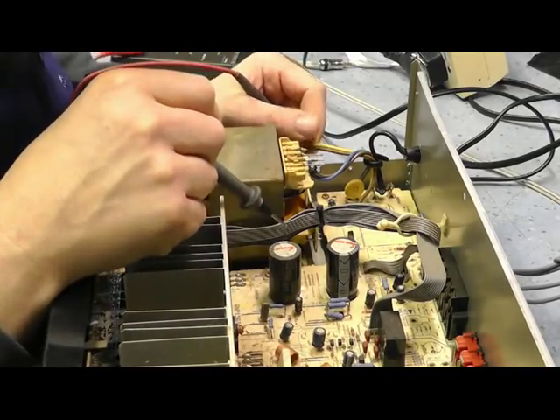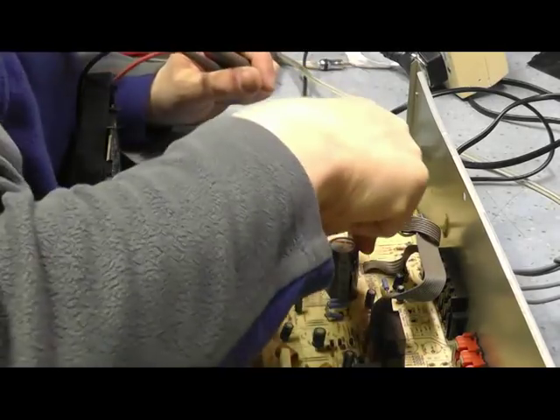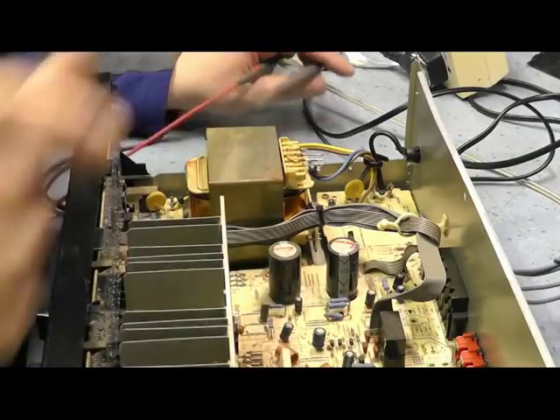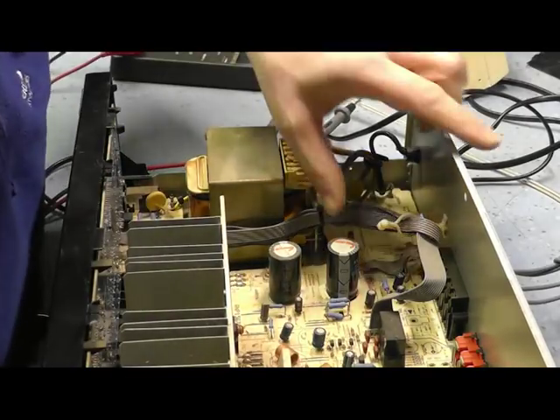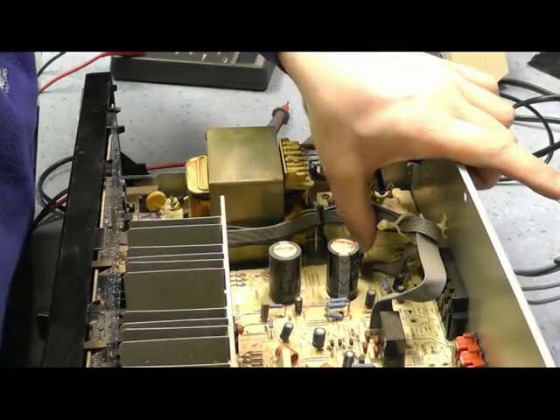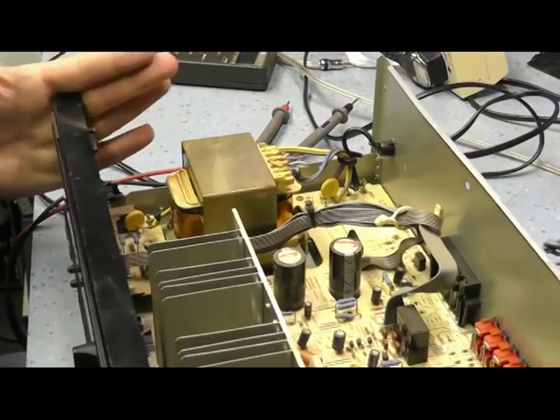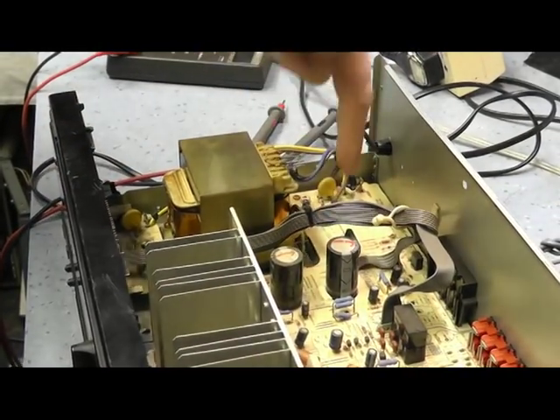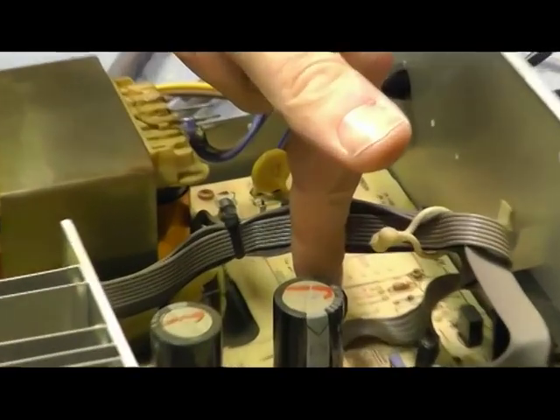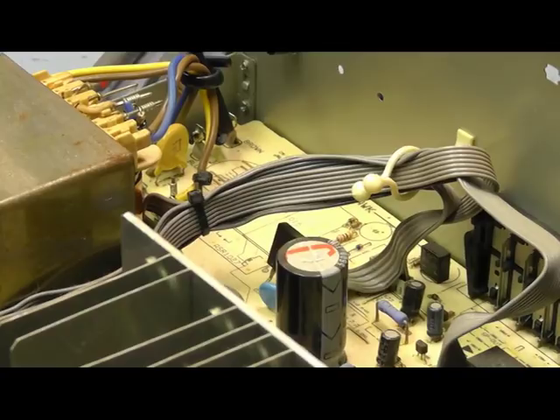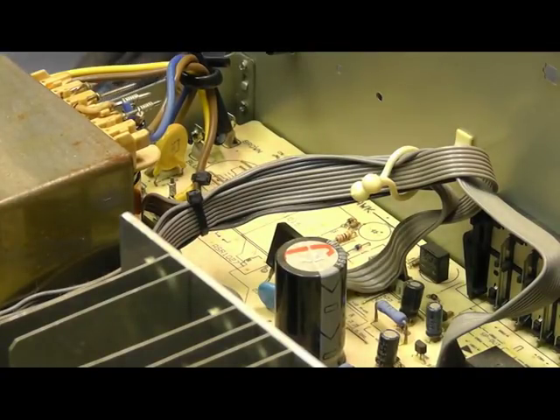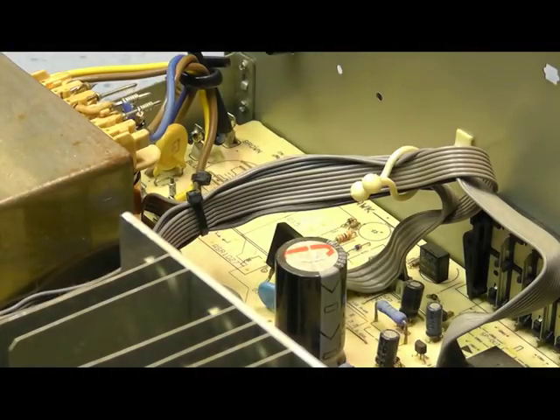Switch is working. So the next thing to do is check our DC link, see if there's any DC supply. What I'm going to do is look down here where we've got the rectifier, behind that capacitor, and check to see if we've got anything coming in on that. I'm still running through the dim bulb to give us a bit of protection against short circuits.